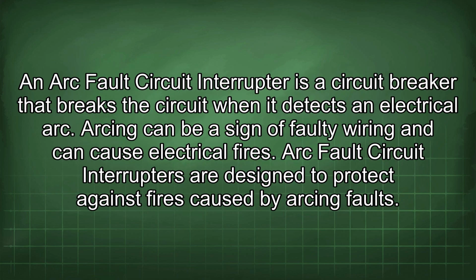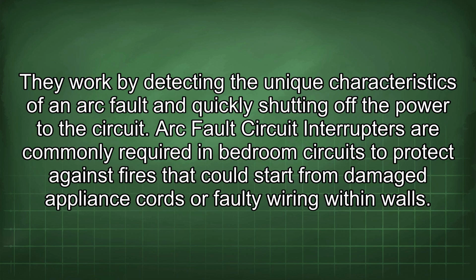An arc fault circuit interrupter is a circuit breaker that breaks the circuit when it detects an electrical arc. Arcing can be a sign of faulty wiring and can cause electrical fires. Arc fault circuit interrupters are designed to protect against fires caused by arcing faults. They work by detecting the unique characteristics of an arc fault and quickly shutting off the power to the circuit. Arc fault circuit interrupters are commonly required in bedroom circuits to protect against fires that could start from damaged appliance cords or faulty wiring within walls.